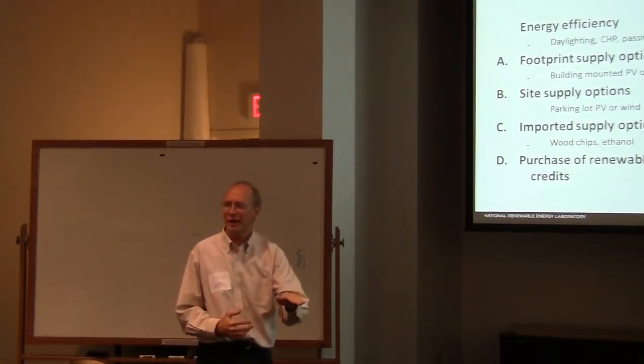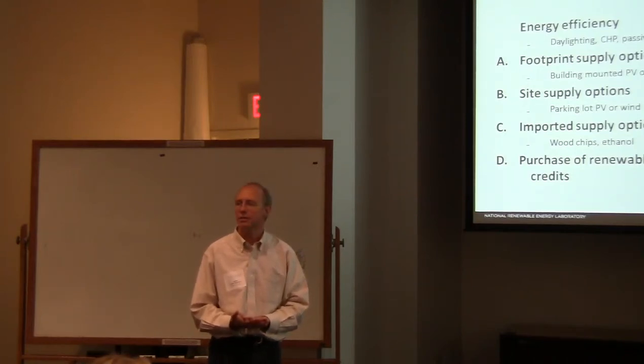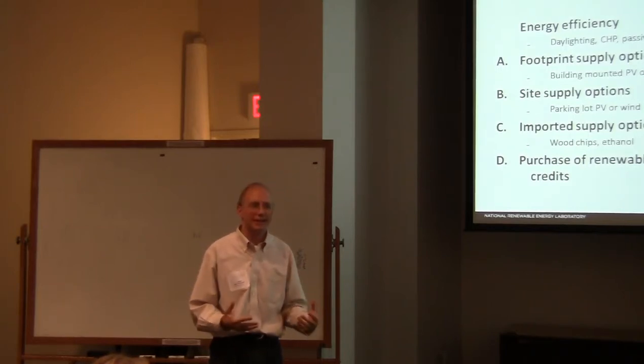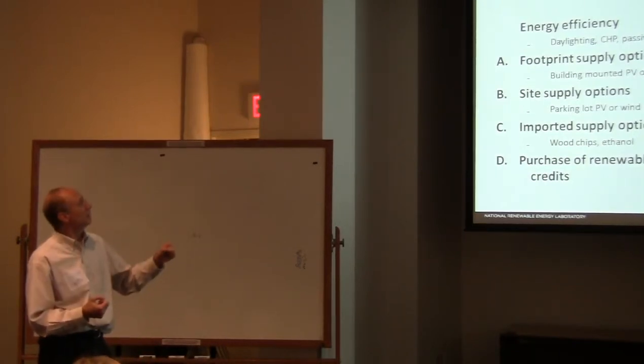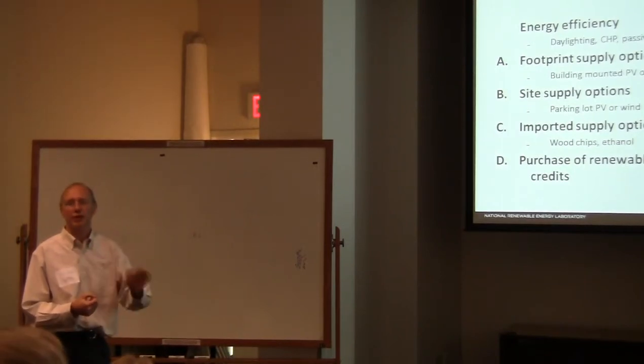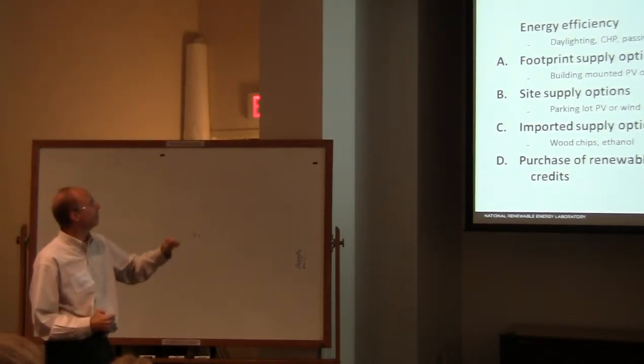Export energy to the grid and do not import energy from the grid, that is actually the best situation you can have. Okay? And you deal with your own storage needs, etc. I don't know of anybody that has achieved that. It's kind of the same problem as being grid independent and truly being zero. In some ways, it's better to be attached to the grid so you can export to the grid, because if you're grid independent, all summer long that PV system basically sits idle because you need so much PV in the wintertime to keep that building running.